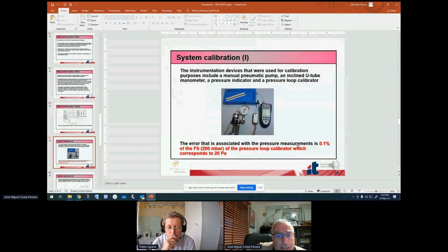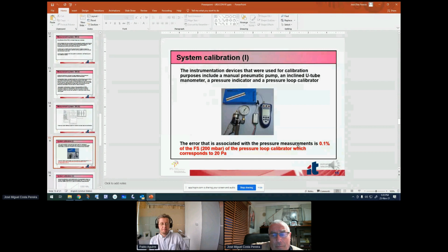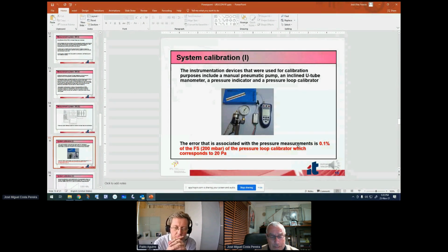Regarding system calibration, that is an important part of the system, because the pressure values that are used to measure and to stimulate non-nutritive sucking are really low. The instrumentation devices used for calibration include a manual pneumatic pump, an inclined U-tube manometer, a pressure indicator, and a pressure loop calibrator, as represented in the figure. With this set of equipment, after calibration, the error associated with the pressure measurements is about 0.1%. This value is relative to the full-scale value of the pressure loop calibrator, which in our case corresponds to 20 Pascal.